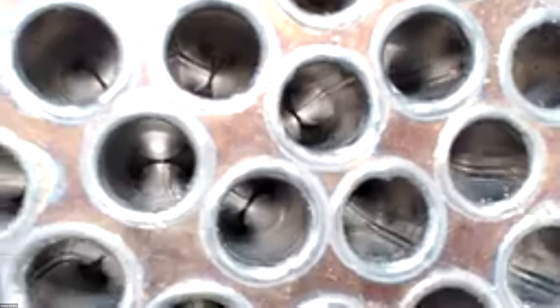We can't get brushes down in through these tubes. These tubes are pinched off every inch or so, so you can't actually push something down through them. So get a good soak on them. Then go ahead, remove the Fernco cap on bottom, let everything drain out. And if you have any of these tubes that are plugged, they'll hold that water. Then you can go ahead and get like a small washing machine hose or a little hose that will fit in these holes, and you can go through and try blowing each one of them out.